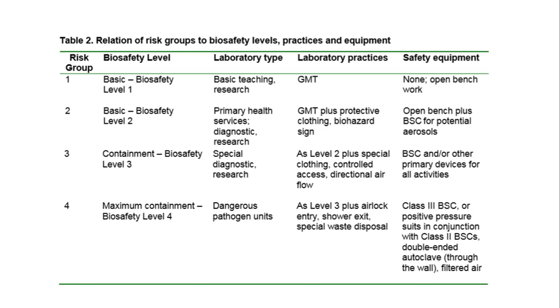BSL-1 requires only good microbiological techniques (GMT); no special safety equipment is required, though laminar airflow can be used. BSL-2 requires GMT plus protective clothing, PPE, and a biohazard sign on the main lab door; open bench plus biosafety cabinet for aerosol protection. BSL-3 includes all BSL-2 requirements plus special clothing, controlled access, and directional airflow — air enters from one direction and exits from another after filtration.